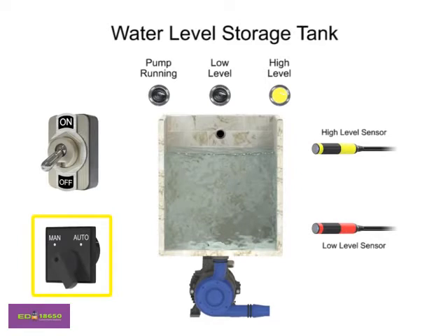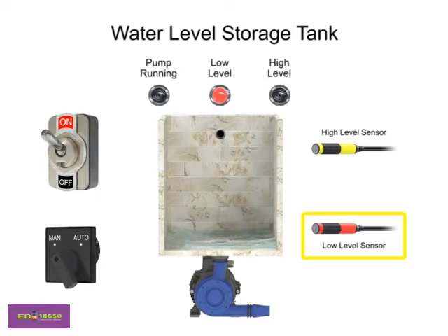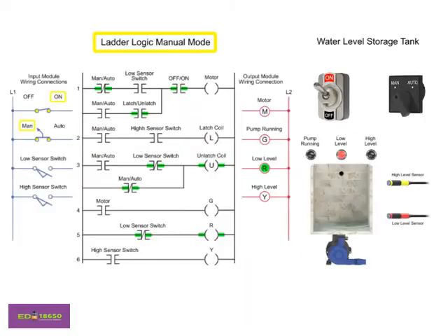In manual mode, the program controls the water level by monitoring the low-sensor switch input. In this mode, the pump motor turns off when the low-sensor switch is off and turns on when the low-sensor switch turns on.